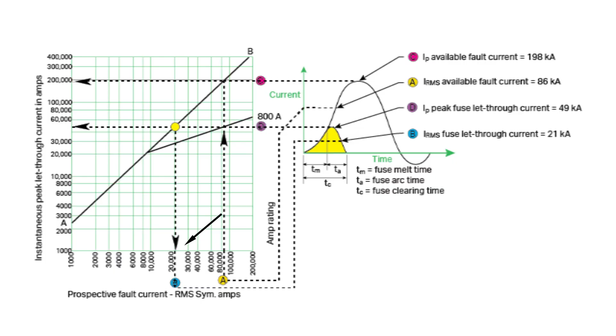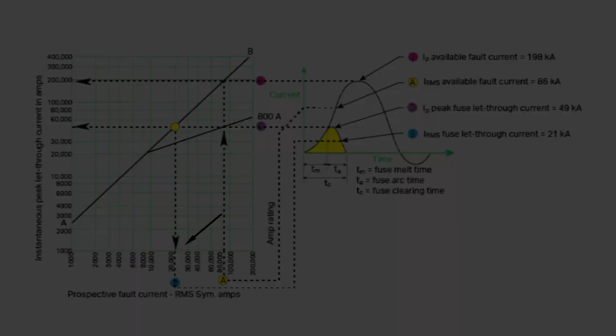To find the apparent prospective RMS let-through current, we use what is referred to as the up, over, and down method. First, enter the curve on the x-axis at 86,000 amps. Then proceed vertically to intersect the 800 amp fuse curve. Then follow horizontally or over to the AB line, then back down to the x-axis to find the RMS let-through value of 21,000 amps for this example.